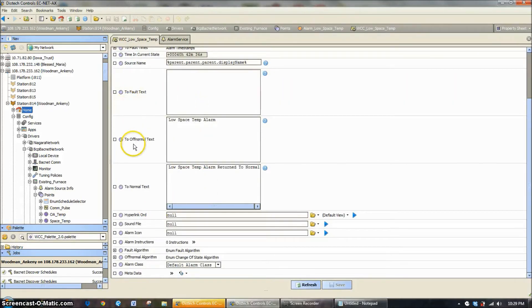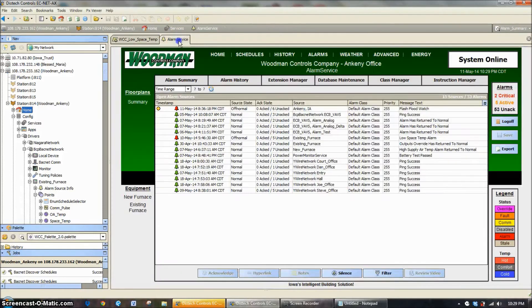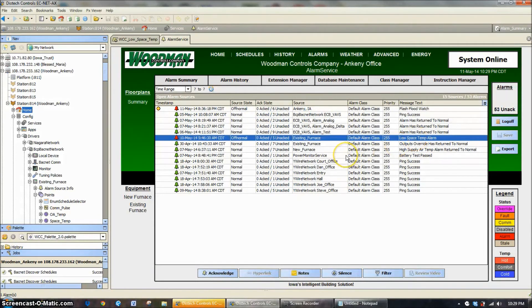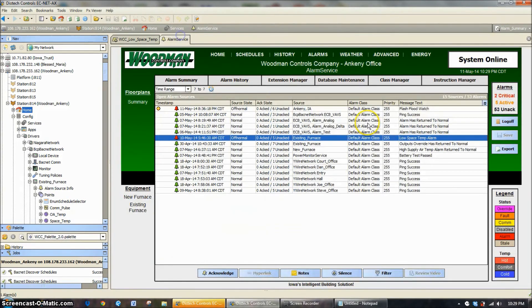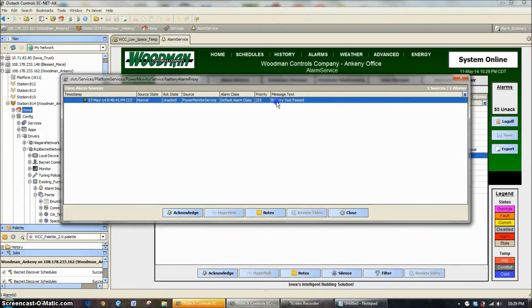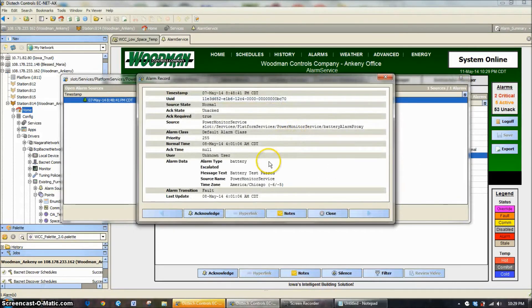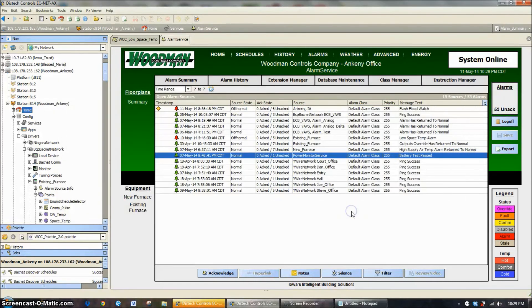Going on down the list, 'to off-normal text' is going to show you what you see on the right-hand side. So you may want it to say some pump alarm or high space temperature alarm, or you may want it to just say 'in alarm' and 'return to normal' — there may not be a need for a whole bunch of explanation. Similarly, going down the list, it's going to display what happens when it returns to normal. So as it returns to normal, you'll see it say 'battery test passed' — at one point we had a battery test fail, and then it went back to battery test passed. So that's its current state.